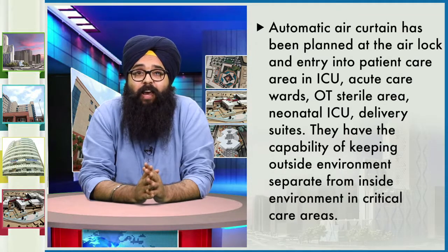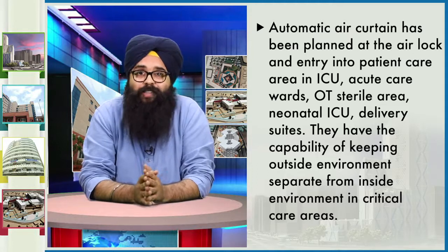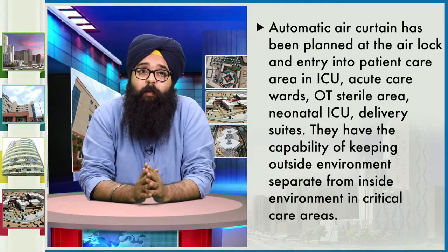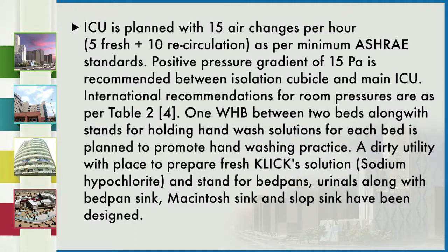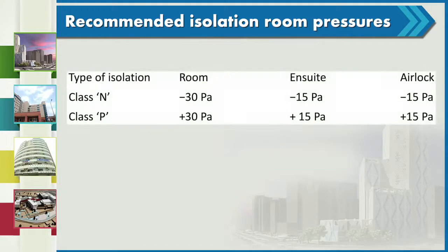Automatic air curtains have been planned at the airlock and entry into patient care areas in the ICU, as well as in acute care wards, OT sterile areas, neonatal ICUs, and delivery suites — keeping the outside environment separate from the inside in critical care areas. The ICU ventilation is planned with 15 air changes per hour — 5 fresh and 10 recirculation — as per minimum ASHRAE standards. A positive pressure gradient of 15 Pascals is recommended between the isolation cubicle and main ICU. International recommendations specify around minus 30 Pascals for Type N rooms, minus 15 Pascals inside the suite, and minus 15 Pascals at the airlock.